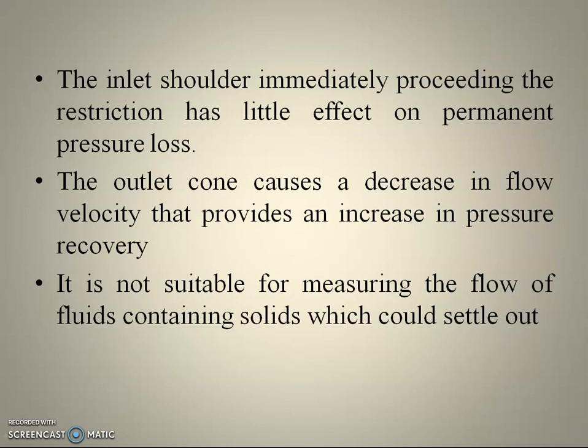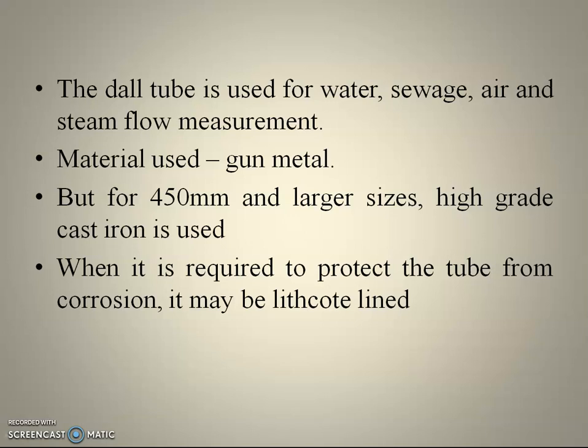The inlet shoulder immediately preceding the restriction has little effect on permanent pressure loss. The outlet cone causes a decrease in flow velocity, which provides an increase in pressure recovery. It is not suitable for measuring the flow of fluids containing solids which could settle out — not suitable for slurry fluids. The DAL tube is used for measuring the flow rate of water, seawater systems, air or gas systems, and steam flow measurement.